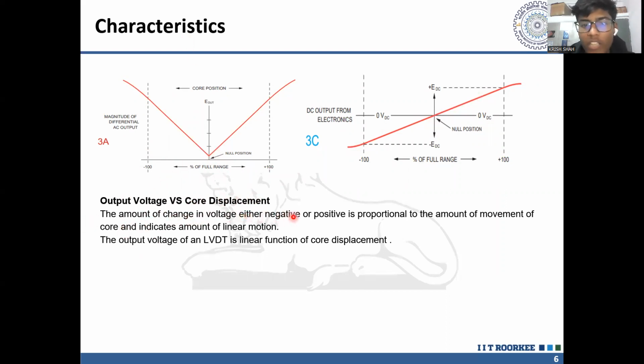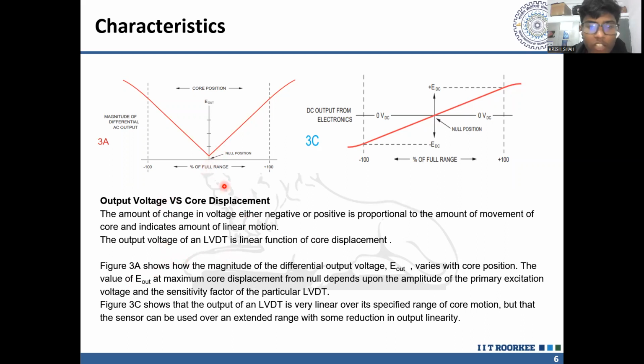The amount of change in voltage, either negative or positive, is proportional to the amount of movement of the core, and it is a linear movement. The output voltage is a linear function for a certain range, of course. Figure 3A shows how the magnitude of the differential voltage E out varies with the core position, and the E out at maximum core displacement from null depends on the amplitude of the primary excitation. At the center of the displacement, it is null, as we said earlier. The EMFs generated in both S1 and S2 will be equal, therefore E out would be 0. And Figure 3C shows the linear range of the LVDT.